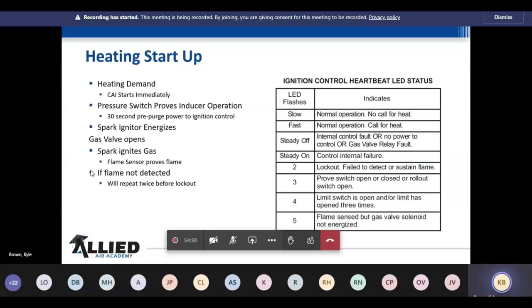And then we want to talk about, and this is just an example of one of the standard boards, spark ignition. There's nothing fancy to it, but this is just an example of the lights and the codes it gives you. The one thing I want to talk about is the second bullet point, pressure switch proven, but the 30-second pre-purge. As big as some of these units are, it is important to make sure that the pre-purge takes place. You want to get any type of byproduct out of there that may have been lingering from the previous cycle, so you don't have any issues or problems.